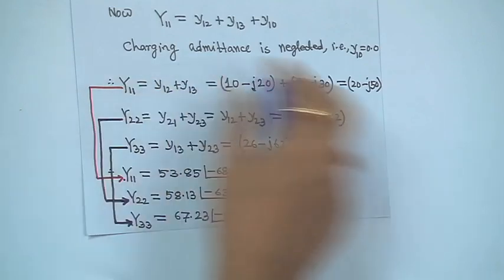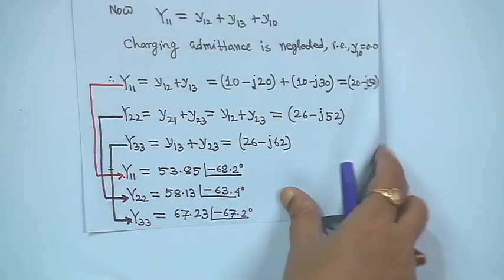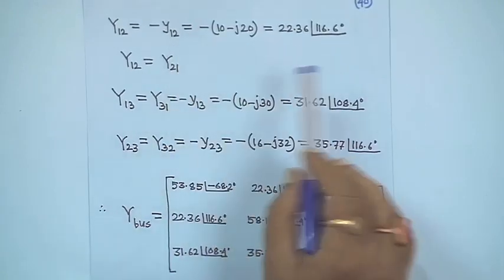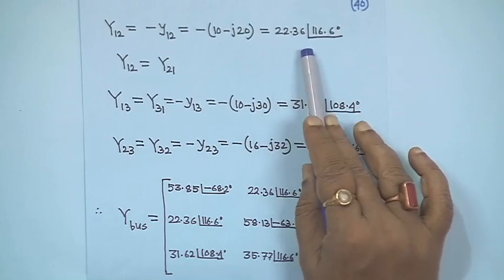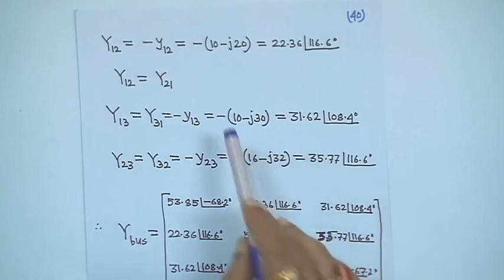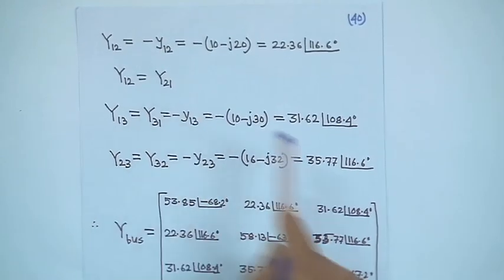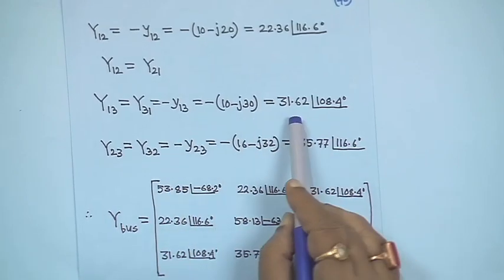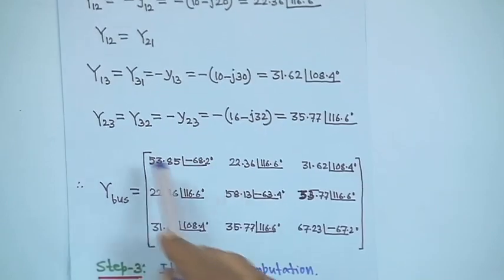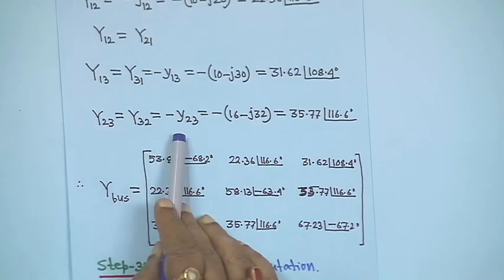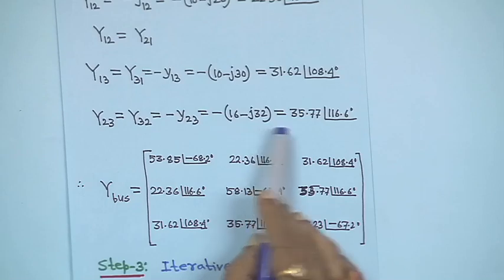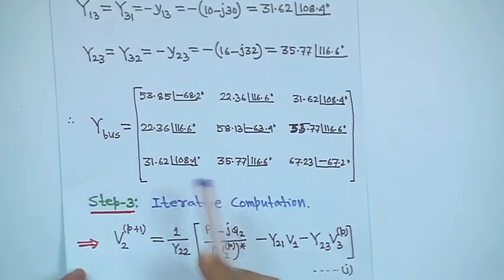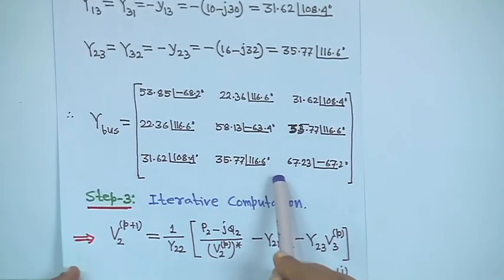The off-diagonal elements are the negatives of the line admittances. Capital Y12 = Y21 = −y12 = −(10−j20), giving 22.36 ∠116.6°. The matrix is symmetric. Y13 = Y31 = −y13 = −(10−j30), giving 31.62 ∠108.4°. Y23 = Y32 = −y23 = −(16−j32), giving 35.77 ∠116.6°. With these, the complete Y-bus matrix Y11, Y12, Y13, etc. is formed.